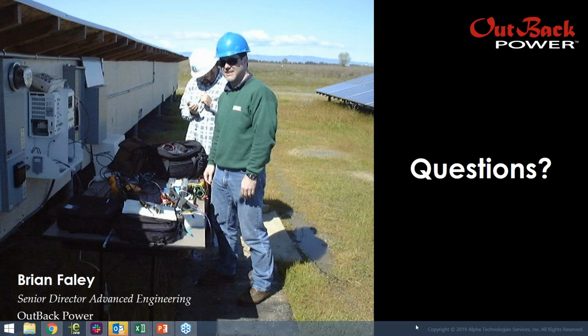Will an inverter lose some of its capacity? No, it shouldn't. At 10 years, if the inverter has electrolytic capacitors inside, those capacitors may not be as good as when they started, depending on how heavily it was used and at what temperature it operated. That's something that can actually be upgraded in some products, but the inverter doesn't really lose capacity — it's just wearing out.